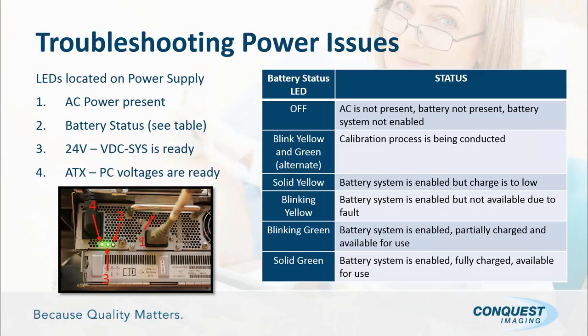So on the back of the system, on your platform power module, again, you'll see some reference to the Voyager platform power module. You have 4 lights, 4 LEDs, and I'm going to describe them. Number 1 is your AC power present. That simply means your system is plugged into the wall. I have an arrow there with the number 1, and I'm not sure you can even see the green light there. It is very, very difficult to see that light. You basically have to get down low and get the right angle to visualize it. But it is there, or if it isn't there, it means you're not getting AC power to the power supply module.